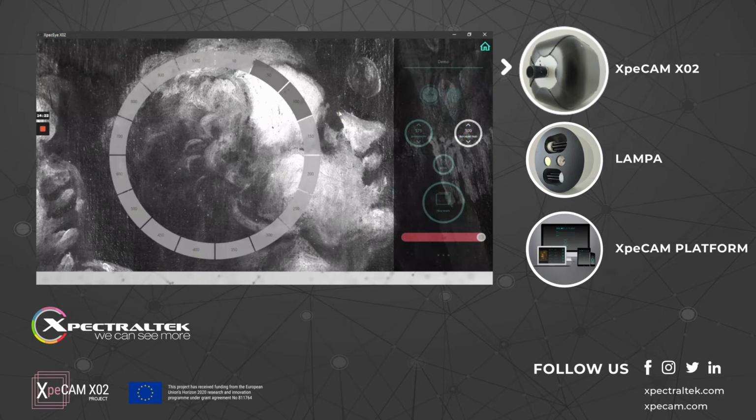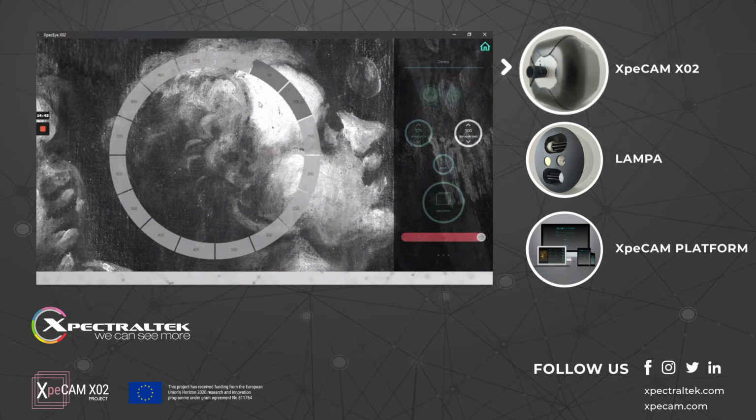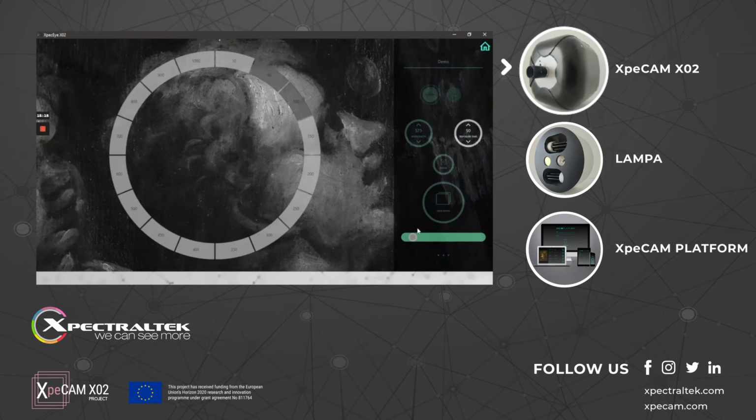So the software is easy for any user to explore, and the easiest part is this green bar at the bottom. When it's good for acquisition, it appears green. When it's bad, some points are saturated. Saturation means that at this point I will not receive any information, because it's too much. Let's imagine that you are blinded by a light source and cannot see anything. Here the same behavior happens: the light is so bright that the camera cannot reach any information. It's blind. So here I will reduce the exposure time, and now it's green, so it's ready to go.